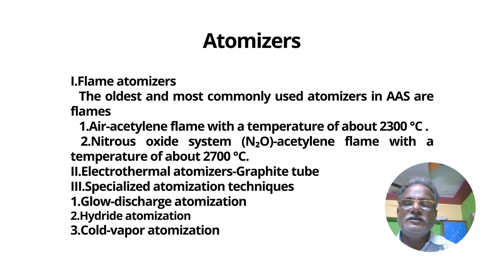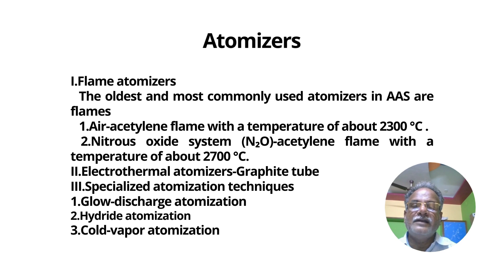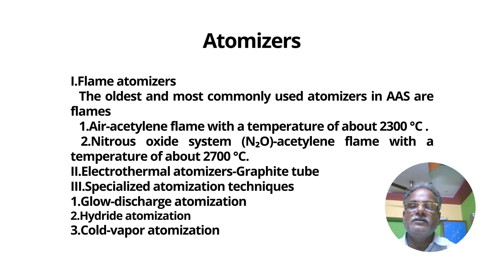The most important component in the atomic absorption spectrometer is the atomizer. There are several types of atomizers: flame atomizers, electrothermal atomizers, and specialized atomization techniques. The oldest and most commonly used atomizers in AAS are flame atomizers. Flames can be generated in two ways: air-acetylene flame and nitrous oxide flame.